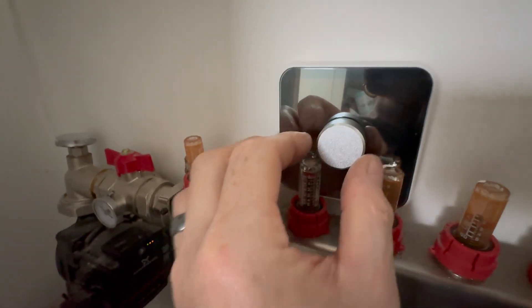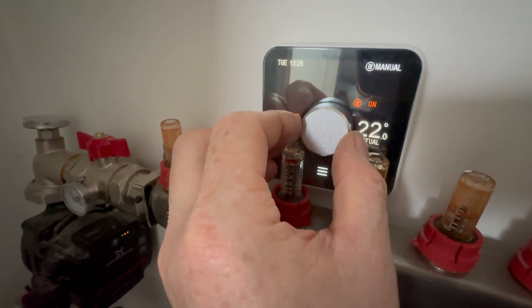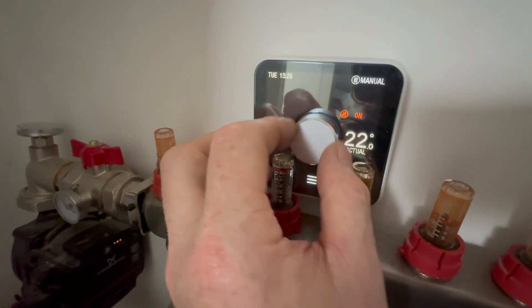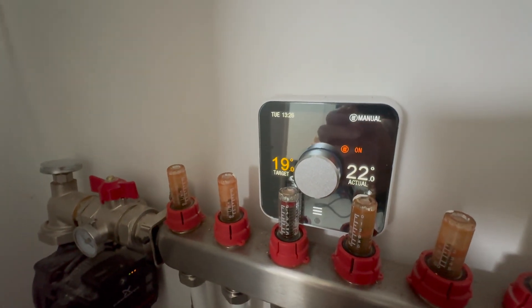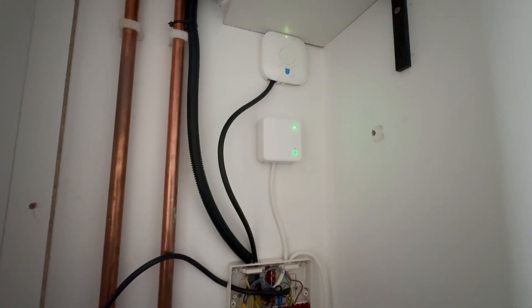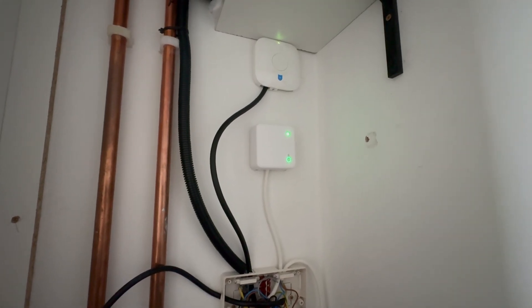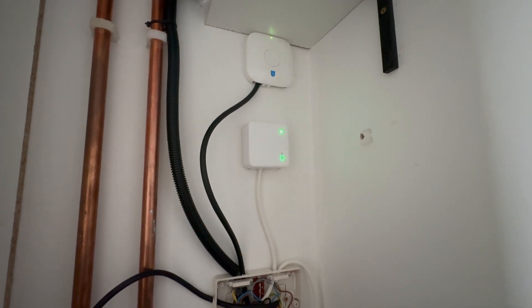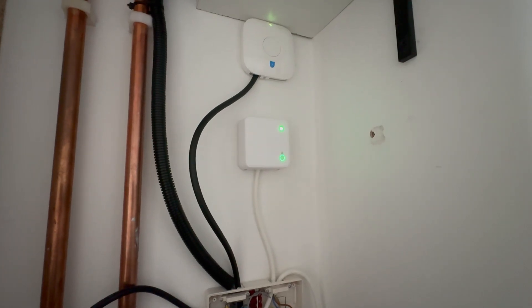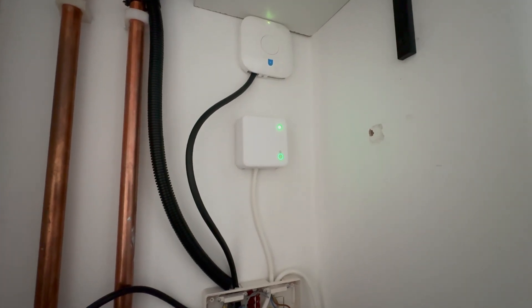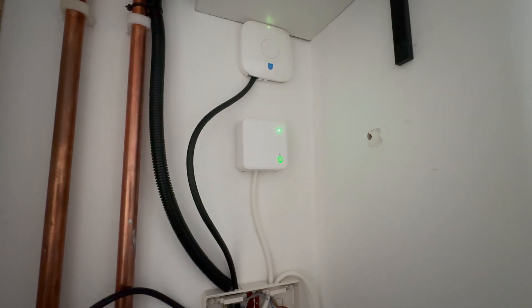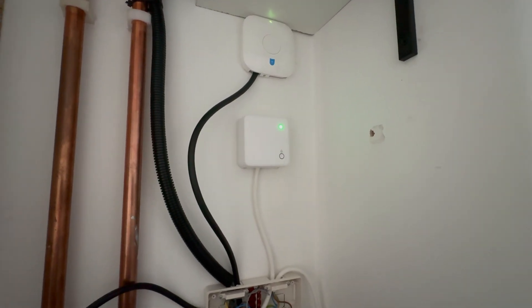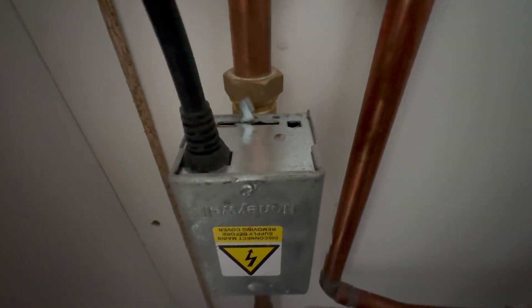Let's turn it off. So in reverse order, press the button in. Turn it lower than the room temperature is. Then we should get the green light start flashing. And then once it goes off we should lose signal to the pump and the zone valve. There we go. So the valve's going back and the pump's gone off. So that's all working.